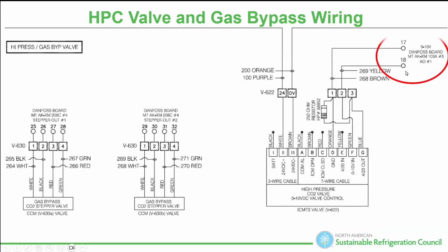Because coming right here, you see 17 and 18 coming off the controller. That's a 0 to 10 volt DC signal coming into these two pins off the yellow and green wire. All right. And so if the valve says 50%, it's open 50%, I expect right here to read 5 volts DC. If this says 48%, I expect to read 4.8 volts DC. That tells me the controller's in charge.